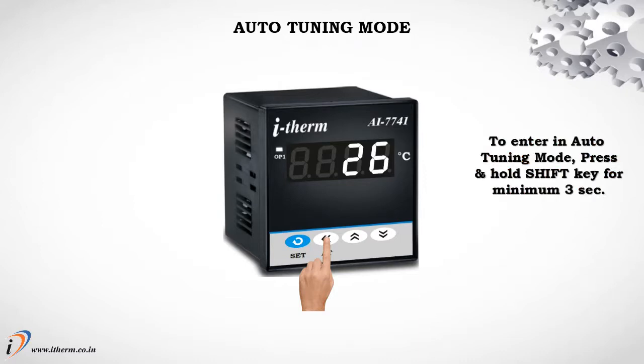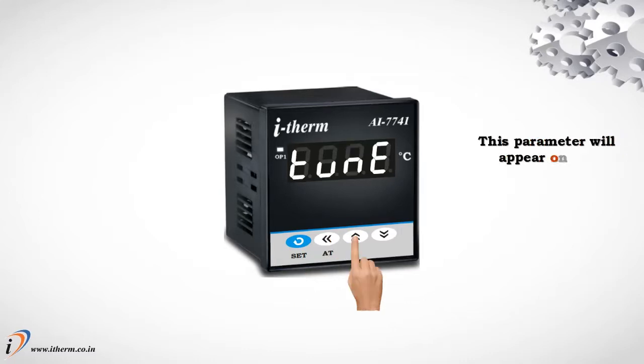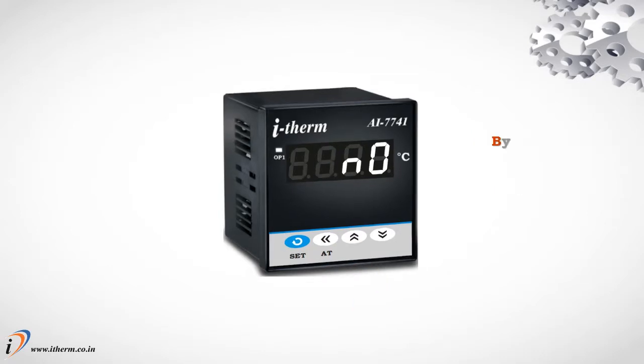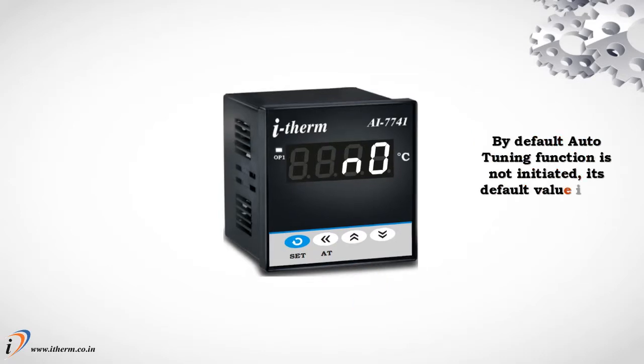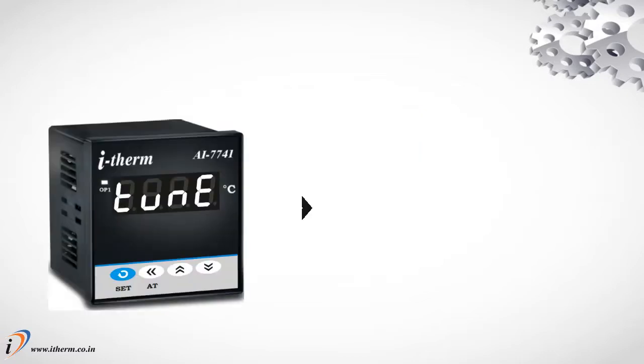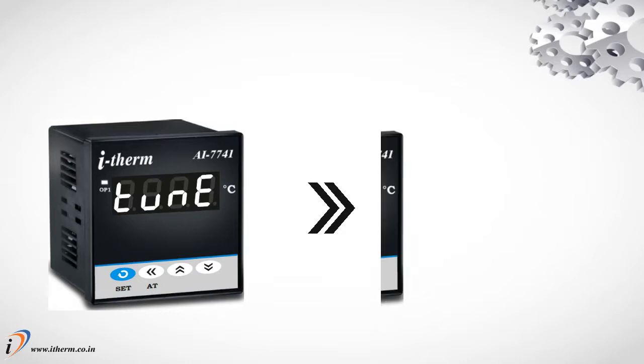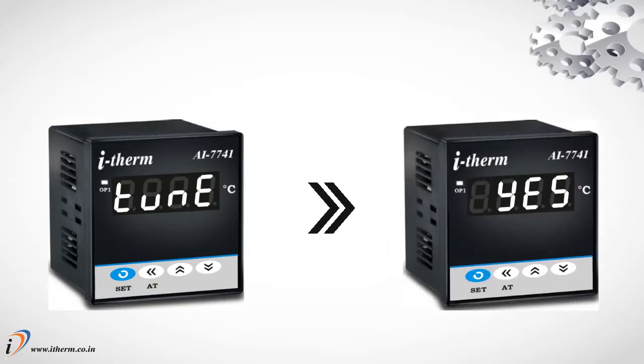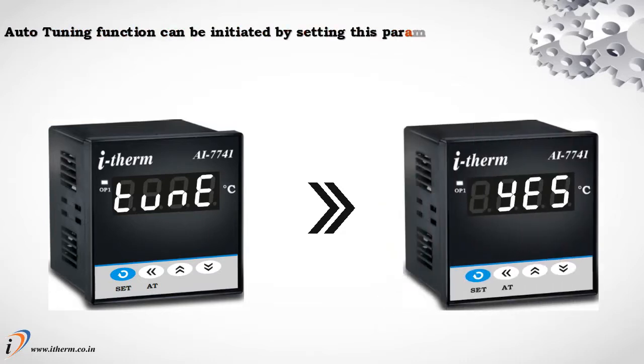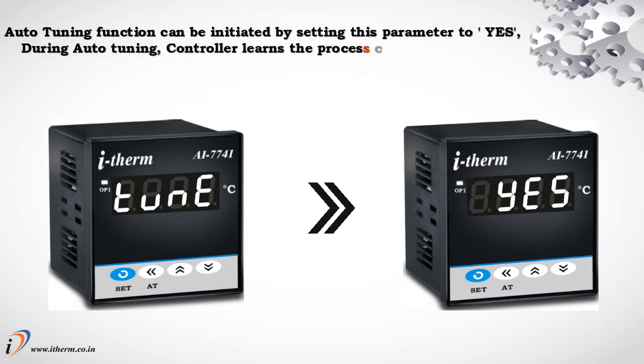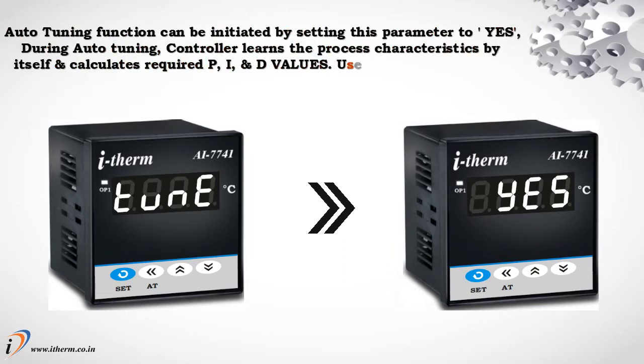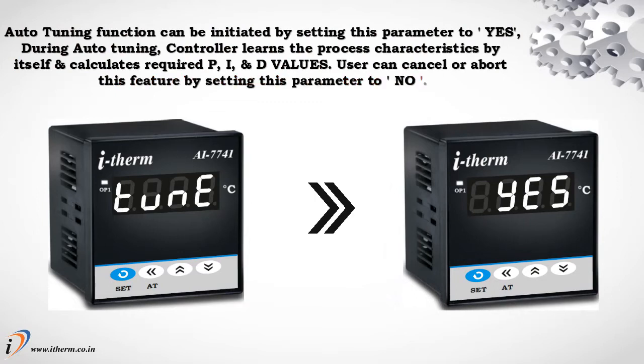Press and hold shift key for minimum 3 seconds. Parameter 1, auto-tune. This parameter will appear only if auto-tuning function is not initiated. Its default value is no. Auto-tuning function can be initiated by setting this parameter to yes. During auto-tuning, controller learns the process characteristics by itself and calculates required P, I, and D values. User can cancel or abort this feature by setting this parameter to no.